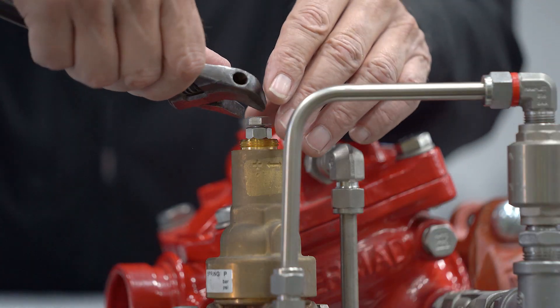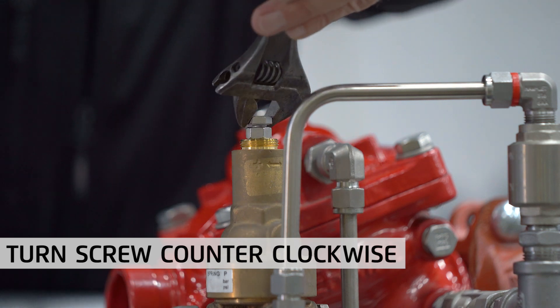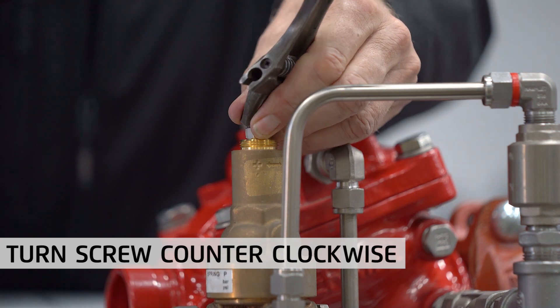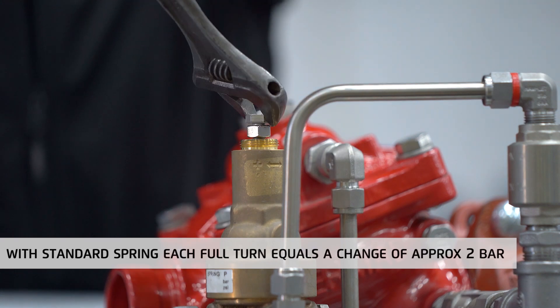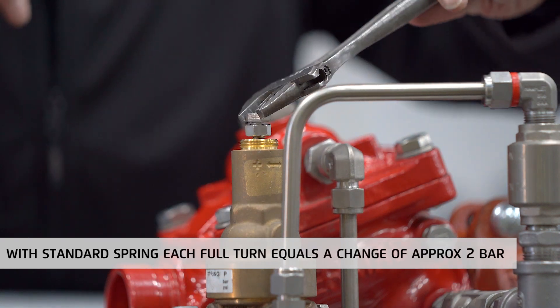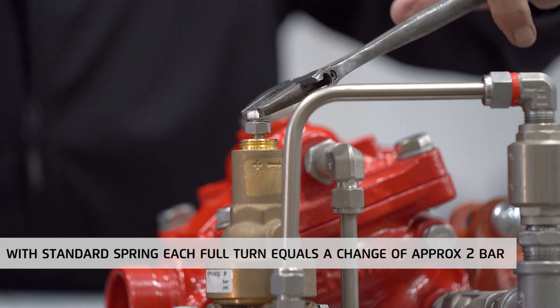To do that, slowly turn the adjusting screw counter-clockwise, thus lowering the set relief pressure, until the valve opens slightly. Note that with the standard spring in the pilot, each full 360-degree turn of the adjusting screw changes the pilot setting by about 2 bars or 28 psi.